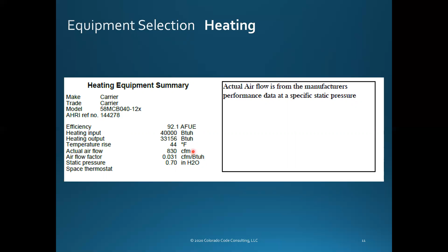And so at 0.7, we're going to look at what heat speed is here on the charts. And this is the other one that you would look for, okay? That little performance data piece that I've just cut and pasted there. And this lower portion here is just a small piece of the CFM. So let's take a look at that example. This one has 4 speeds: high, medium high, medium low, and low. Let's just prove this here. Here's a 0.1, and they said it was 1125 at heating. 0.1, medium low is 1125. Isn't that amazing? This is what the manufacturer will call it, shipped at heat speed. So it'll be shipped at medium low.